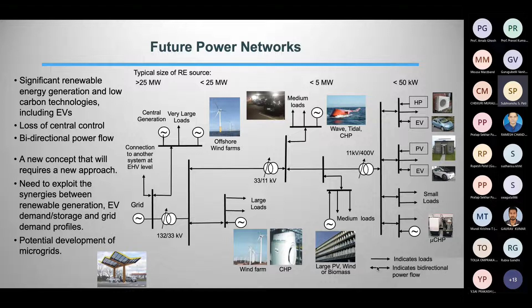Looking at the impact now of voltage profiles of the grid with renewable energy generation - well first, without renewable energy generation, this is how it is designed now. We have tap changers on transformers, and these tap changers keep the voltage at the sending end here to the left at a fixed value, and then this tap changer here on the 66 to 11 kV transformer tries to adjust the voltage, push it up and adjust it to a fixed value.